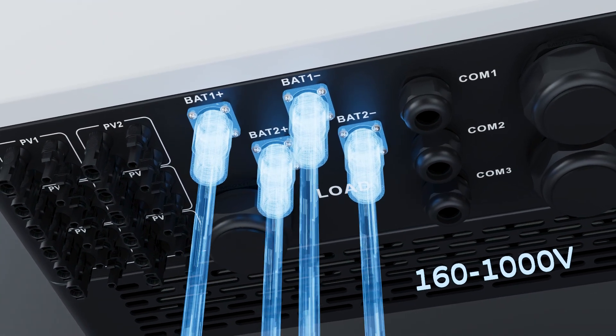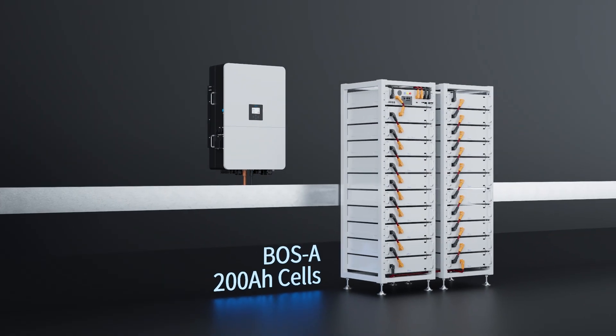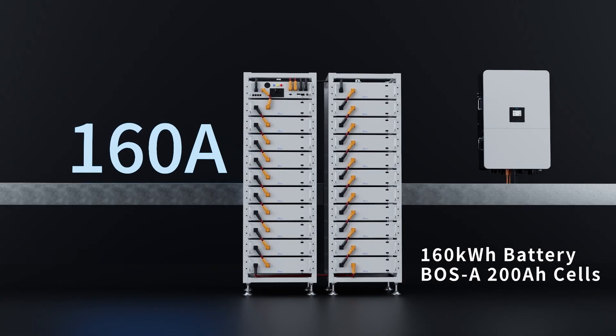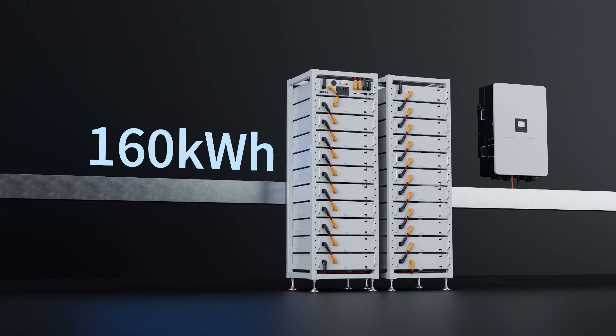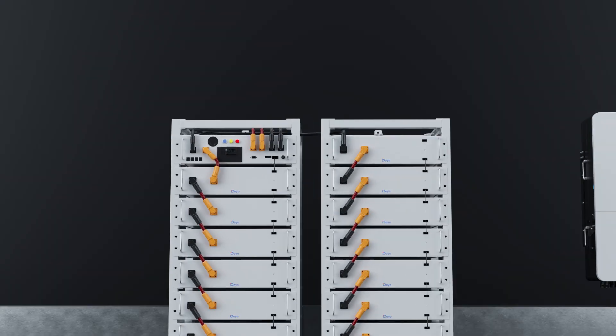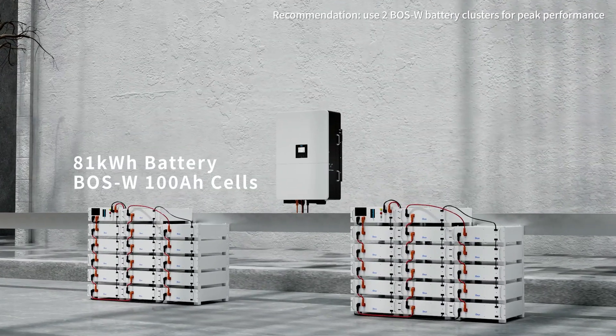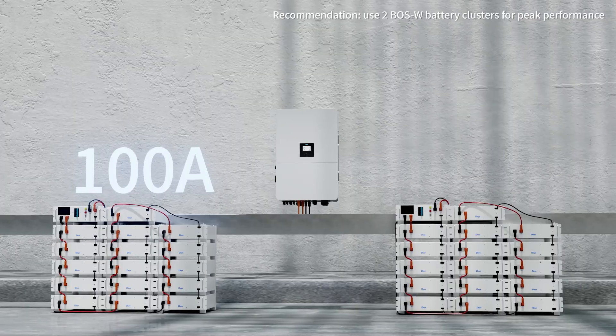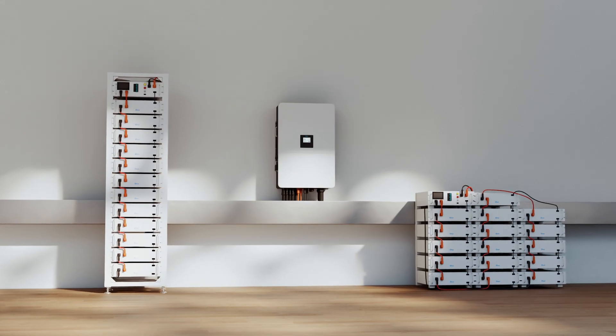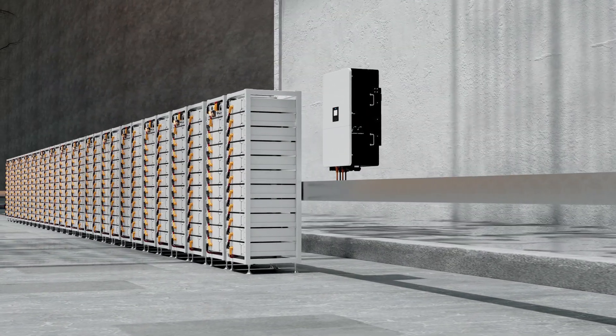On the battery side, performance is significantly enhanced, with a battery voltage range of 160 to 1,000 volts and two independent battery ports. The BOS-A delivers up to 160 amperes charge and discharge currents with a single cluster capacity of 160 kilowatt-hours. It features dual battery ports matching the inverter's design, reducing cable size and cost, and offers rack-mounted installation with flexible capacity options. BOS-W provides 100 amperes charge and discharge currents with a single cluster capacity of up to 81 kilowatt-hours, supporting simple bracket or rack-mounted installation for versatile applications. These batteries support 16 clusters in parallel on the DC side, delivering extended backup power.